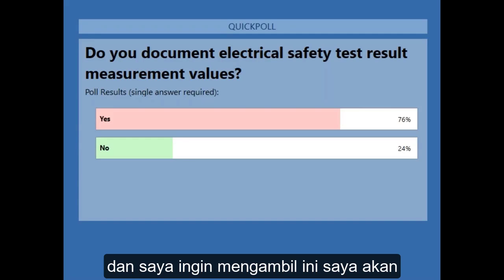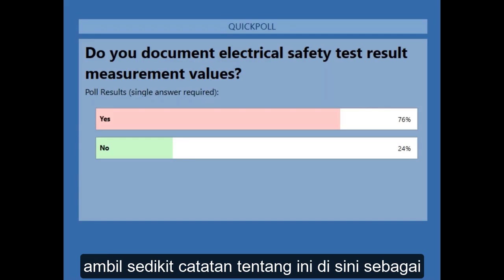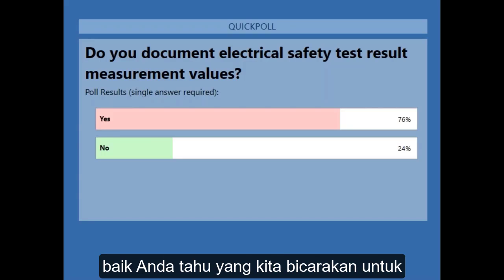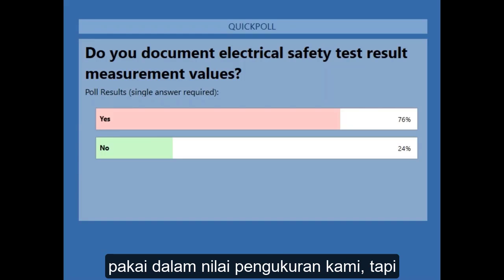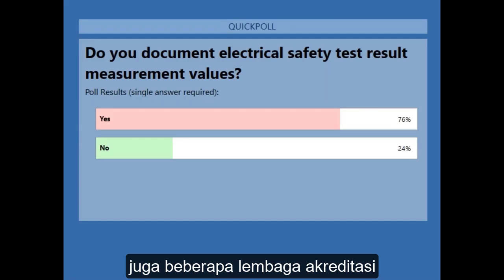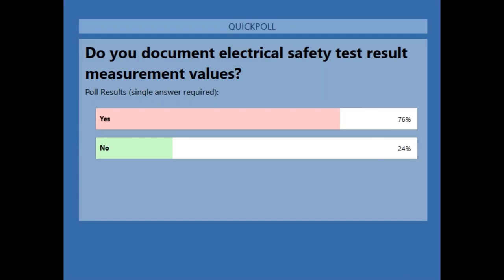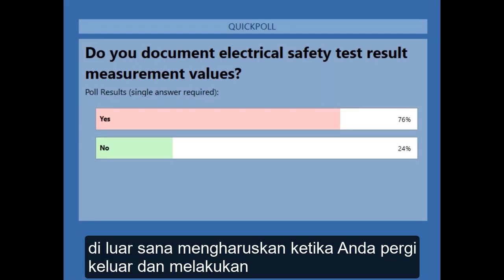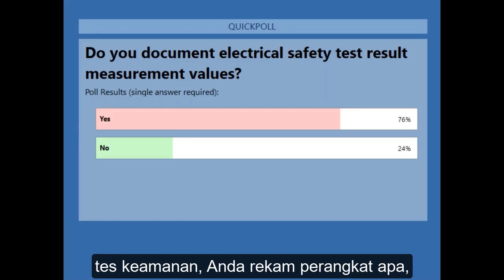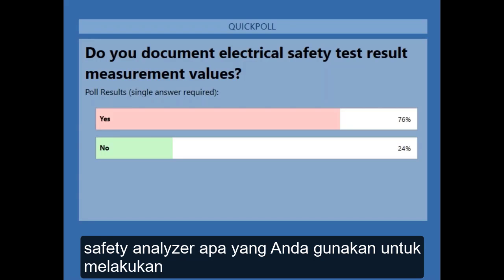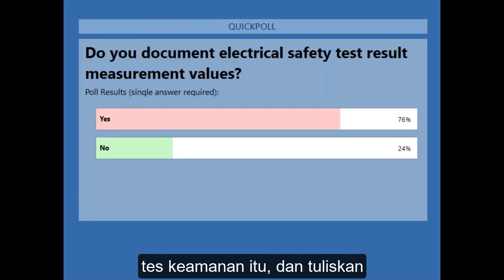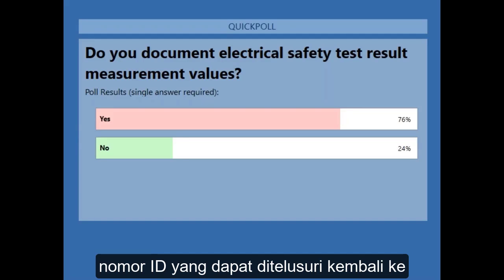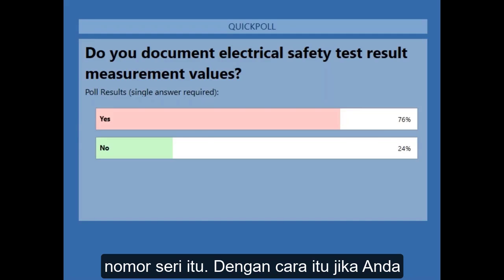And I'm going to take a little side note on this here as well. We're talking about putting on our measurement values, but also some of the accreditation agencies out there require that when you go out and do a safety test, you record what safety analyzer you're using to do that safety test with, and either record the serial number of the device or your ID number, which can be traced back to that serial number.